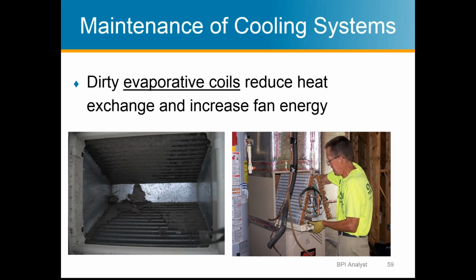And this is why you want a good filter on. You never want to run your system without a filter, because as you plug up this evap coil, it increases static pressure in your system and decreases the efficiency of your system, and it's going to shorten the lifespan of your system as well. So, the higher the MERV filter, it's going to keep the evap coil even cleaner. But like I said, systems are designed for a certain rating, and the static pressure is very important. Evap coils should be cleaned periodically, just so that they don't look like the one on the left. You hire the guy on the right to keep it clean.